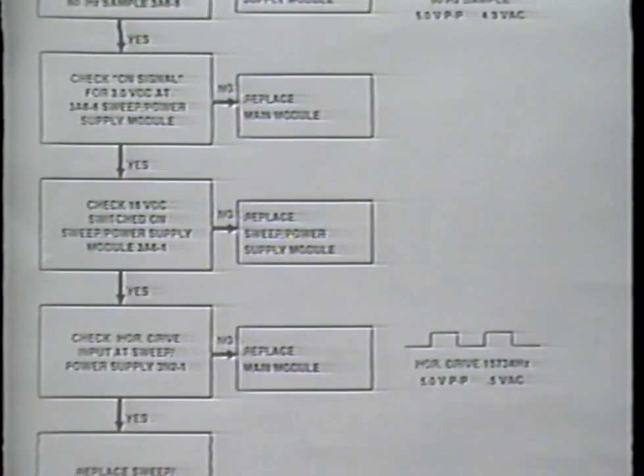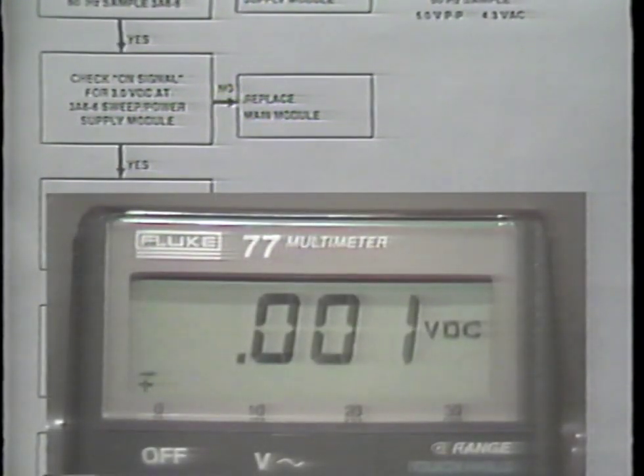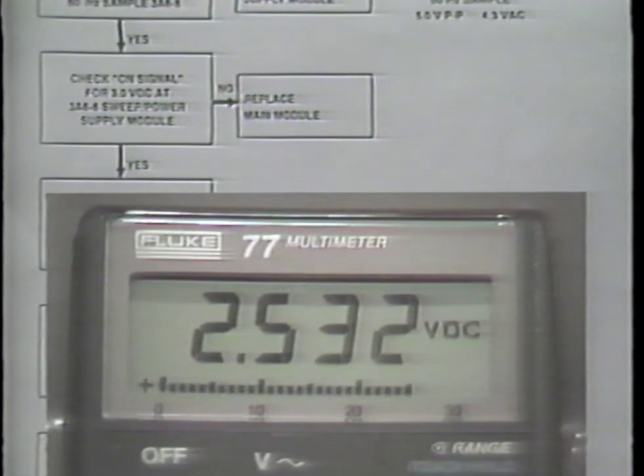Next, check for the on signal at connector 3A6 pin 6. We're going to put the meter probe at connector 3A6 pin 6 and turn the set on and look for a reading of approximately 3 volts DC.